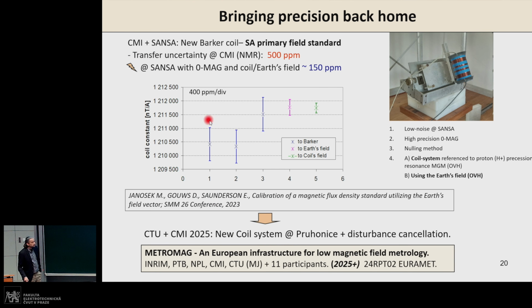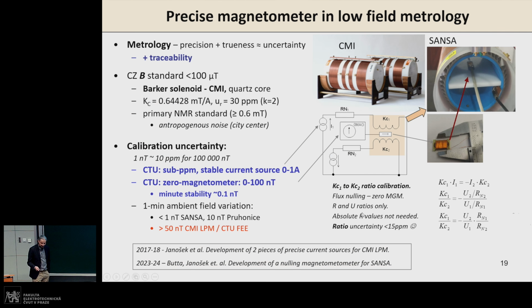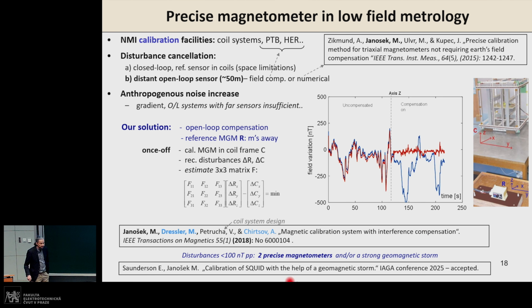And while I was doing these trials also at the Space Agency in Hermanus, we found that by using only the Earth's field and proton magnetometers or the calibrated coil system, we were actually able to achieve an uncertainty about 3 times lower than what the Metrology Institute is providing us. So, as the title of the slide says, we are trying to bring the precision back home, and we are now part of a European grant of EURAMET with the name European Infrastructure for Low Magnetic Field Metrology, and the role of the CTU is to establish a new coil system in Průhonice and a disturbance cancellation system utilizing the idea we have published in this article.